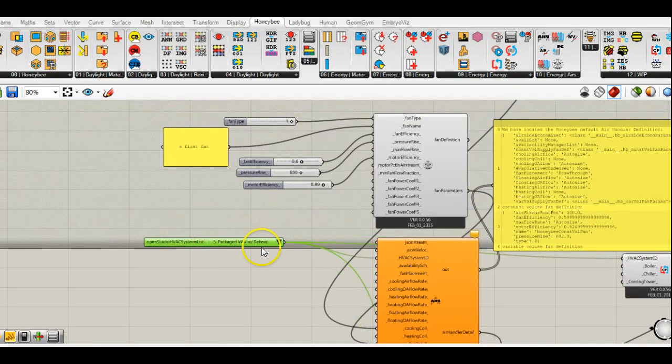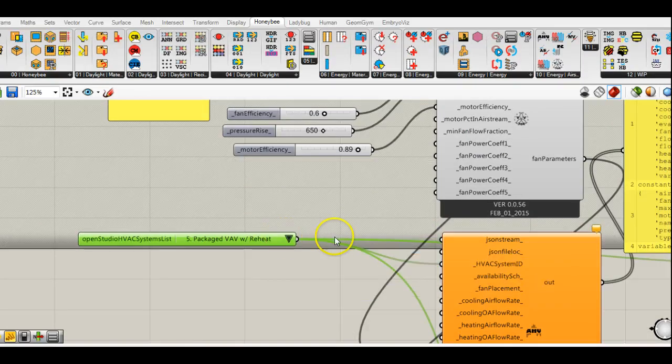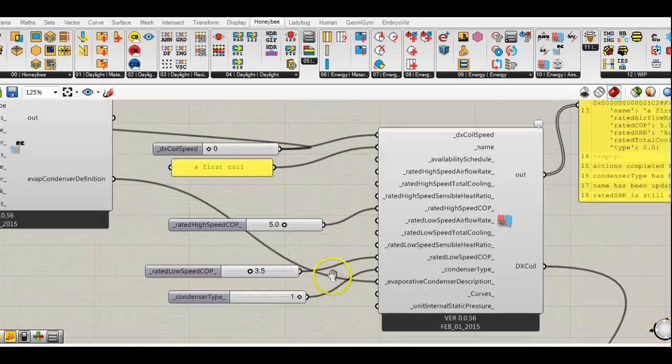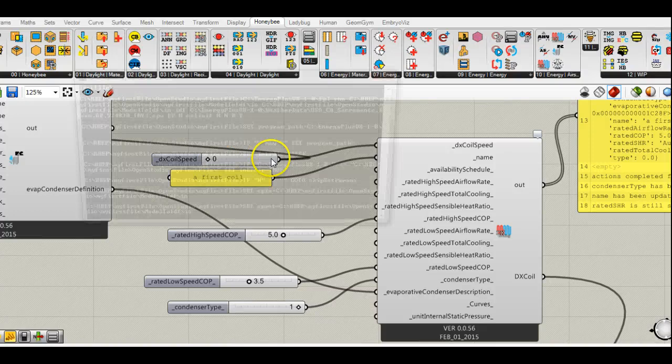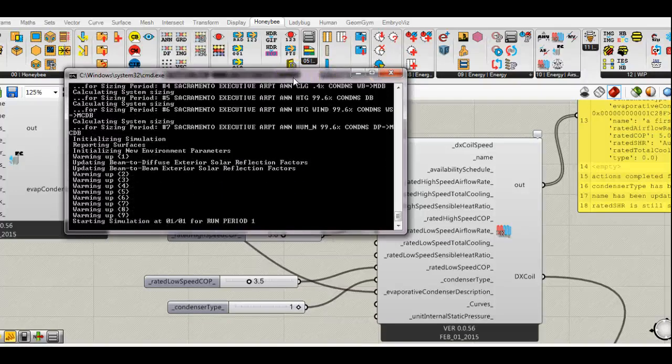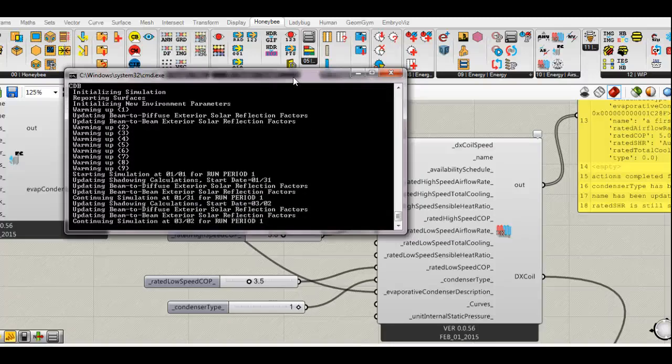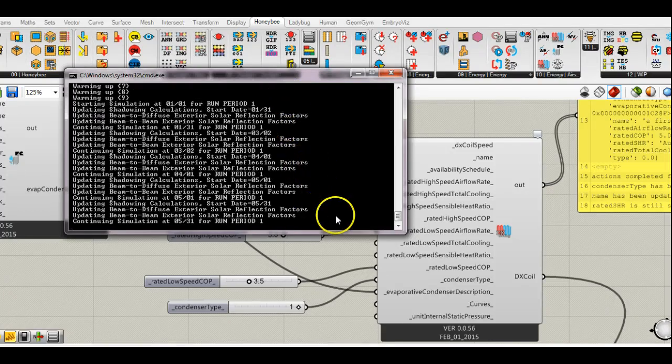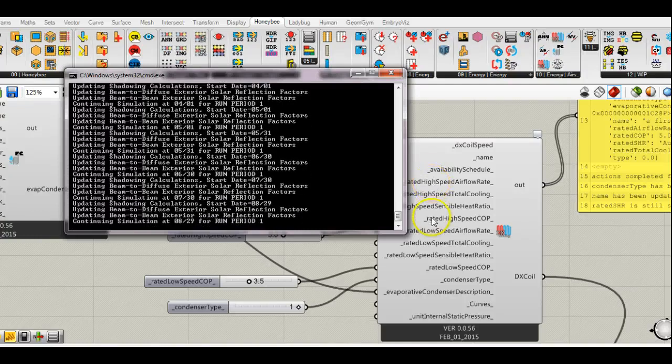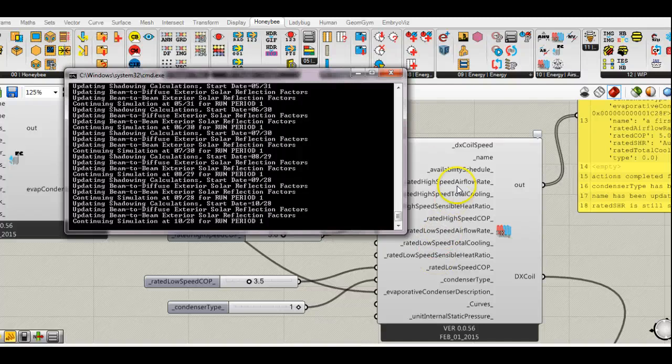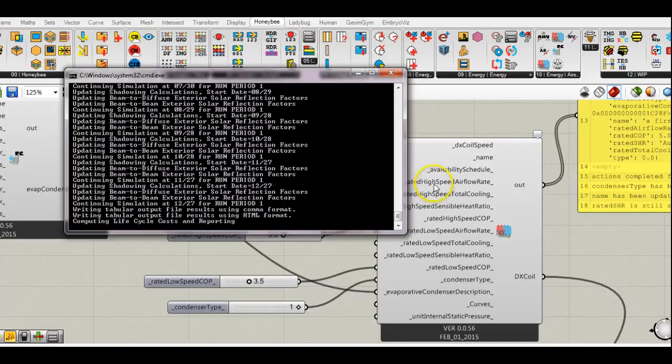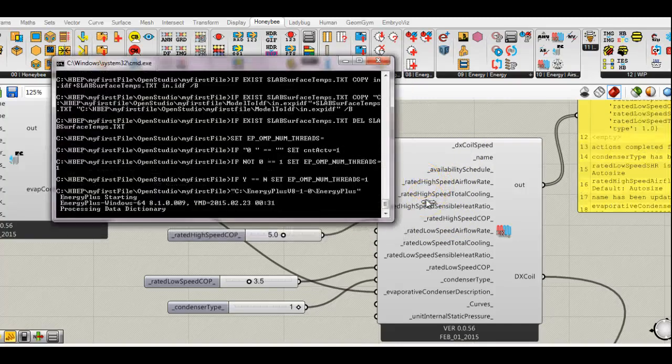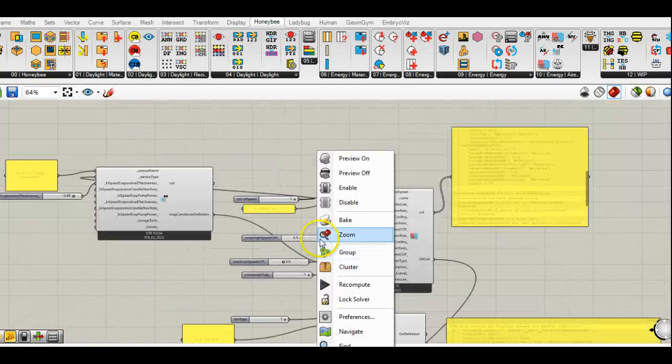So right now we're in a somewhat of an error state. And the reason is because we're using system type five, which normally requires a two speed DX cooling coil. But you can see here that we only are using a one speed DX coil at the moment. So if we change this to a, well, we'll let that run. But you see that actually had a good effect there. So I'll just keep talking while this is running. You might note that we have entries for high speed and low speed. So what happens if you only select a one speed cooling coil? Well, basically, this component will only read or only pay attention to the high speed portions.